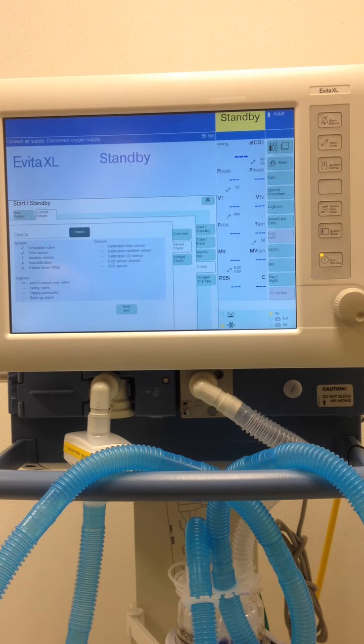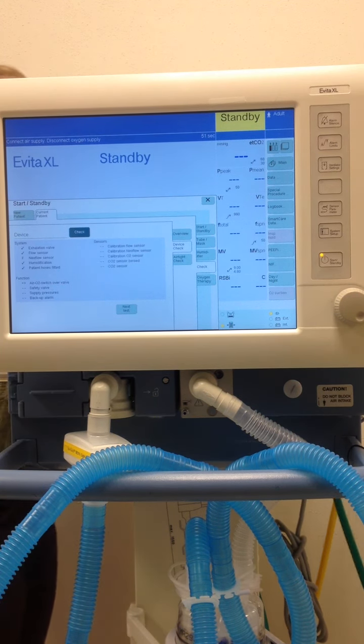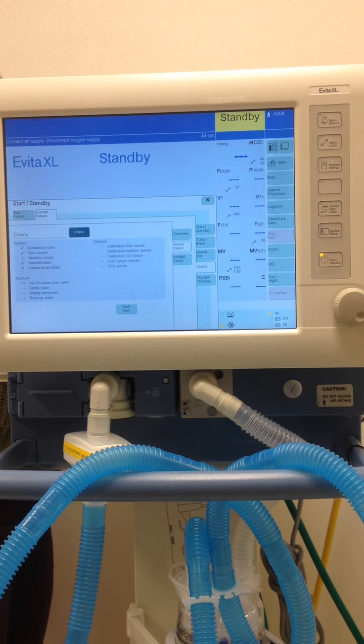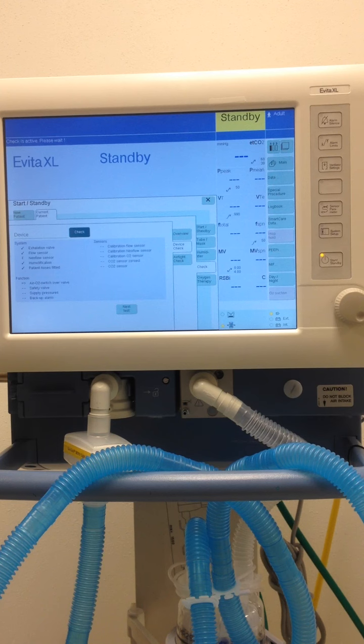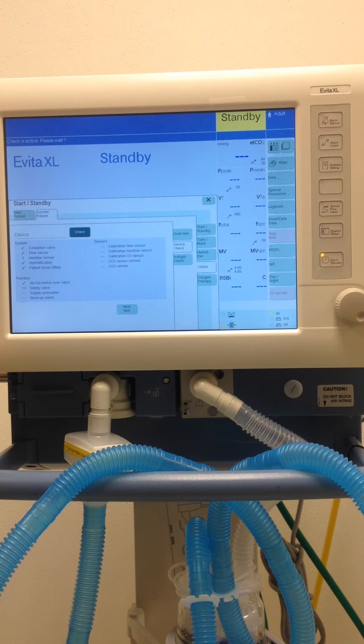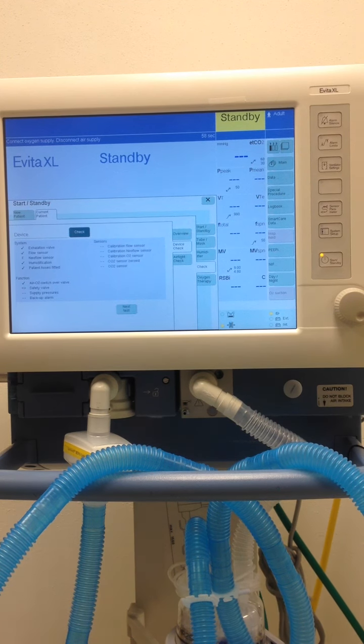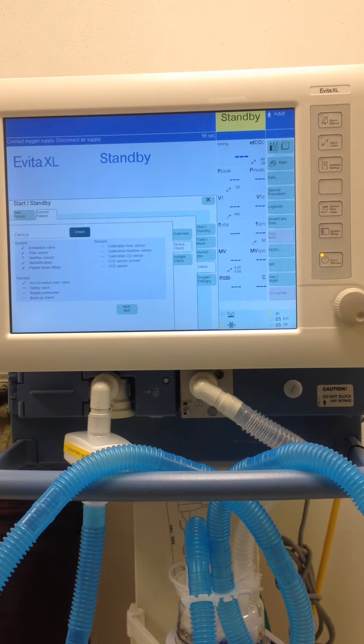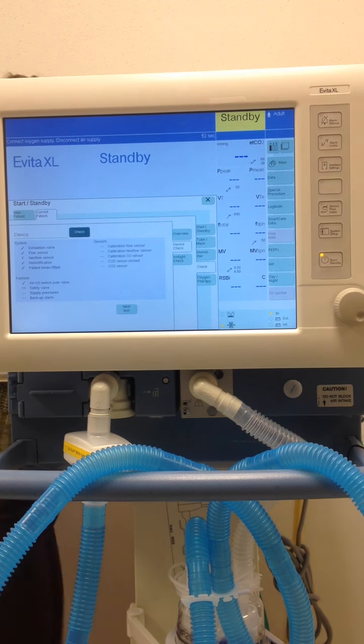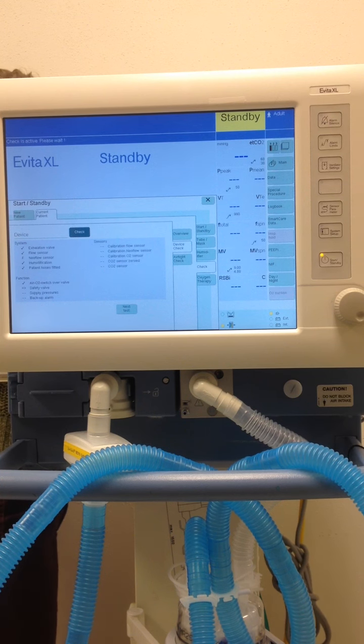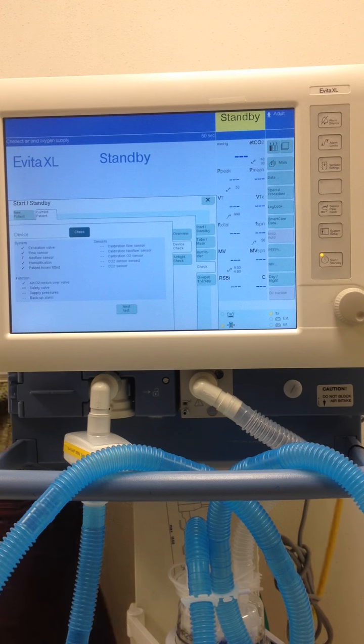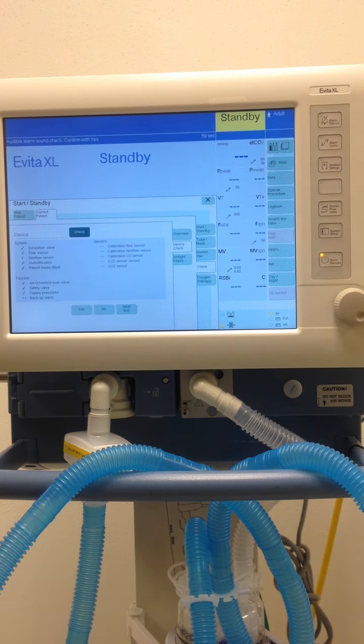So connect air supply, disconnect oxygen supply. So you're basically going to come to the back of the ventilator, wait for the change, you're going to hear your vent, and it's going to tell you check is active, and it'll tell you when to reconnect. So connect oxygen and disconnect air. Okay, audible alarm. Yes, we can hear that. And now it's going to calibrate your flow. Calibration is okay.